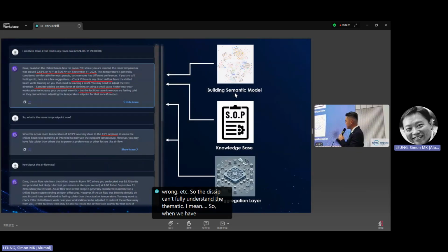So when we have the standardized naming and also the semantic model, we can have some fancy applications. For example, my boss, Dave, feels cold in his room. Now we can use the AI chatbot to answer this question. Because of the semantic model, it knows that Dave, my boss, is in this room, and this room has this VAV box, and it knows the temperature of this room and also the set point, the air flow rate, so it can diagnose the whole process through the AI. That's one application, and this is applied in our tower.